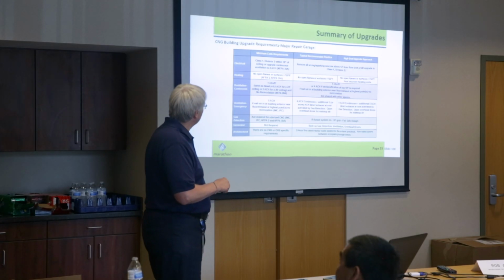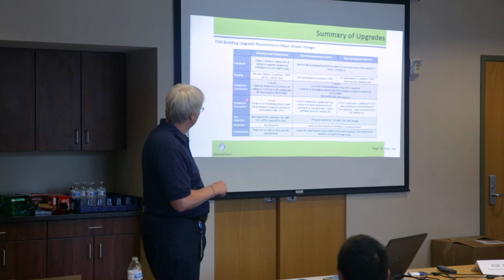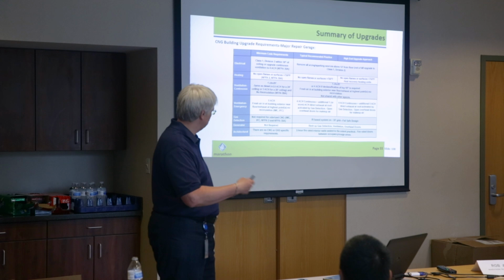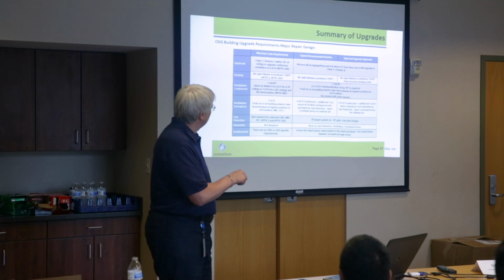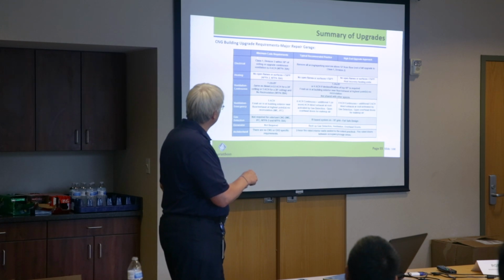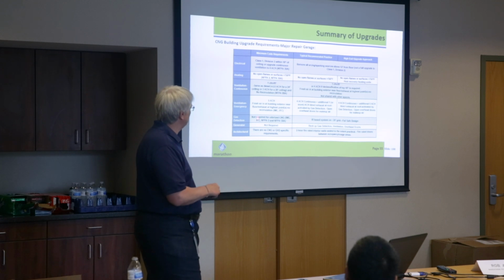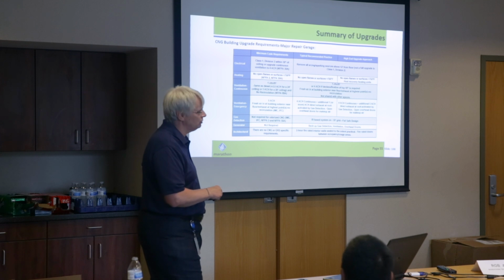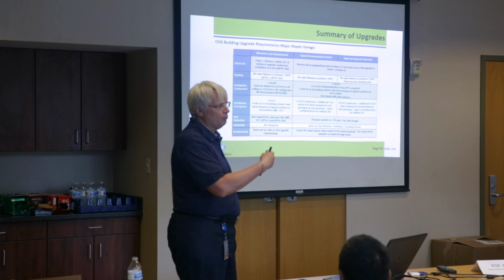Okay, so we divided this up. You can see the different aspects here: electrical, heating, ventilating. We got ventilation continuous, which would be your baseline. We got ventilation emergency, so that's supplemental to the baseline. And we've done a good, better, best approach so that you can see this left column is the absolute minimum that you can do here. So this is what the code says, you know, thou shalt do these things. But in many cases, industry practice is to go beyond that.